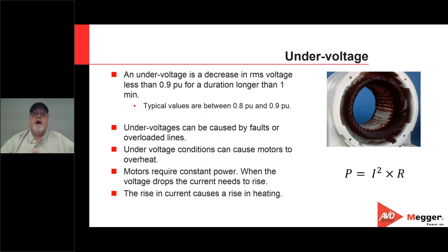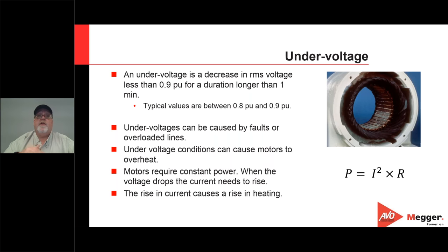Under voltage is defined as a decrease in the RMS voltage of less than 0.9 per-unit for a duration longer than one minute. So 0.9 per-unit means basically 90% of the voltage — if my voltage is 100 volts and it drops below 90, I'm below my 0.9 per-unit. For an under voltage to occur, it also has to last longer than one minute. That's important for an under voltage scenario.